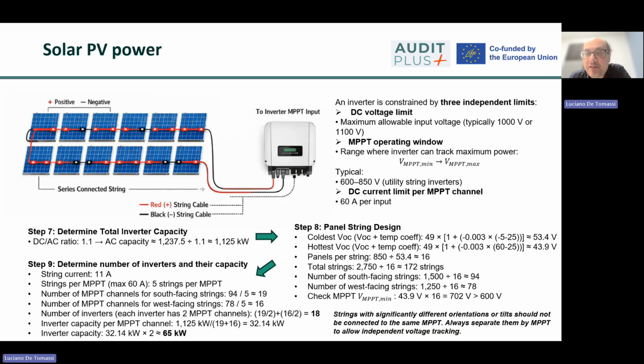Determining total inverter capacity comes after the DC side of the PV system has been broadly sized, and it is driven by both installed PV array size and the expected operating conditions. Inverter capacity is expressed in kilowatt AC and is usually selected so that the DC to AC ratio, often called inverter loading ratio, is within a practical range, commonly around 1.1 to 1.3 for many commercial systems. This means, for example, a 1000 kilowatt peak PV array might be paired with 800 or 900 kilowatts of inverter capacity. The goal is to balance cost, efficiency, and clipping losses. Undersizing inverters reduces capital cost, but can cause some energy clipping at peak irradiance, while oversizing reduces clipping but increases equipment cost and may reduce utilization efficiency.